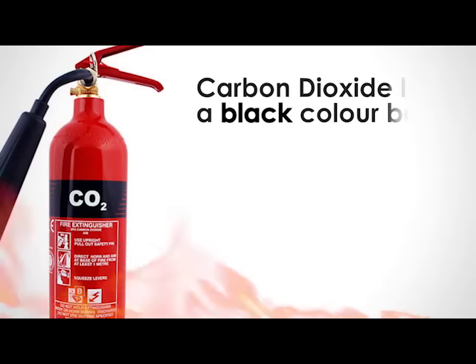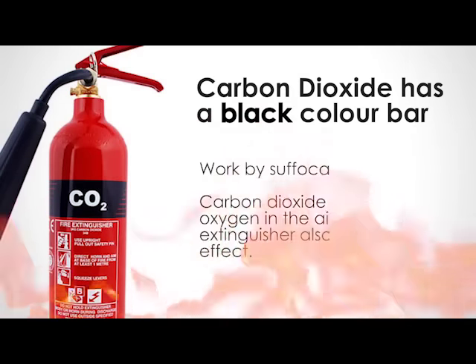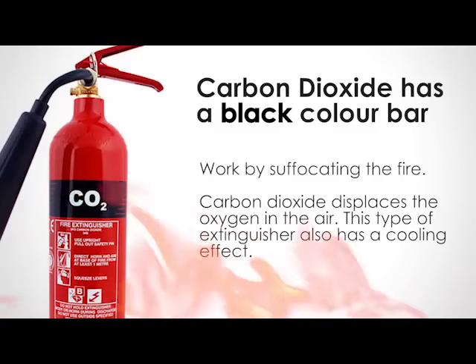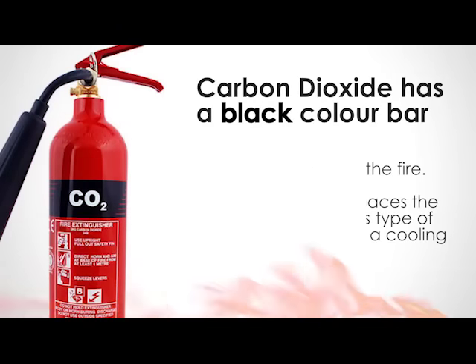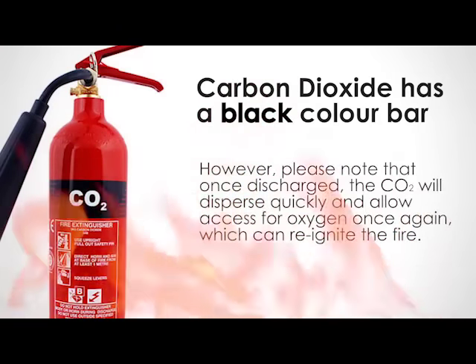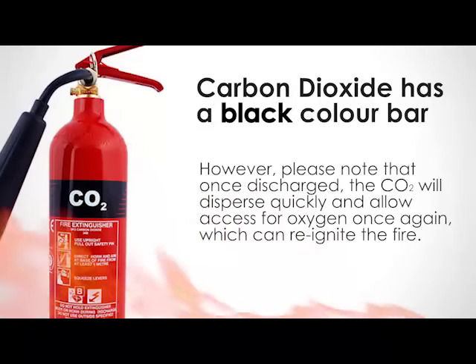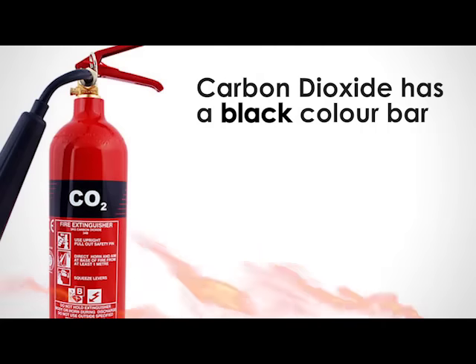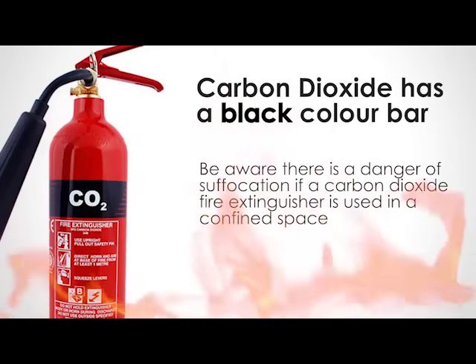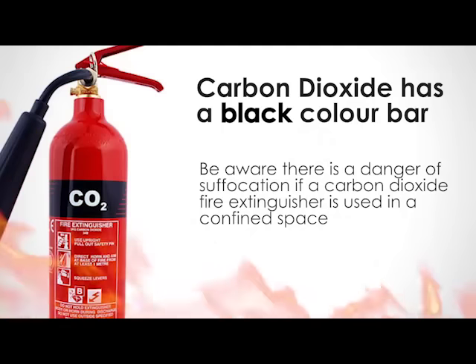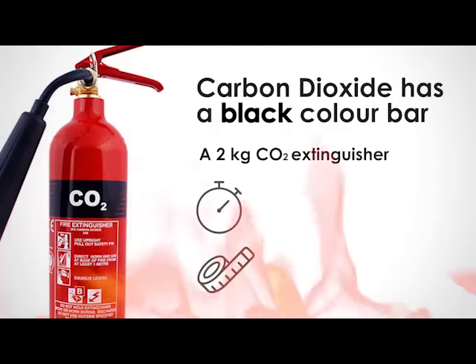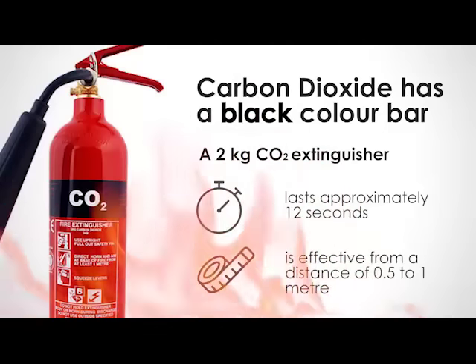Carbon dioxide. This has a black colour bar. Carbon dioxide extinguishers work by suffocating the fire. Carbon dioxide displaces the oxygen in the air. This type of extinguisher also has a cooling effect. However, please note that once discharged, the CO2 will disperse quickly and allow access for oxygen once again. This can then reignite the fire. Be aware there is a danger of suffocation if a carbon dioxide fire extinguisher is used in a confined space. A 2 kilogram total discharge CO2 extinguisher will last for approximately 12 seconds and is effective from a distance of 0.5 to 1 metre.